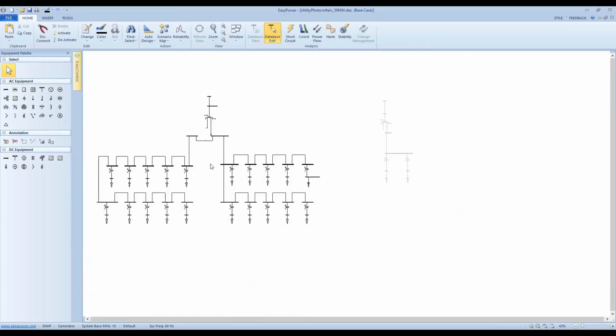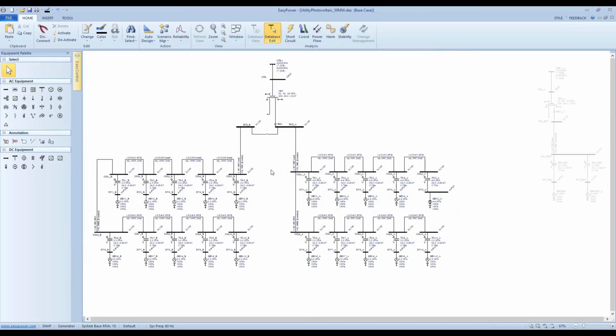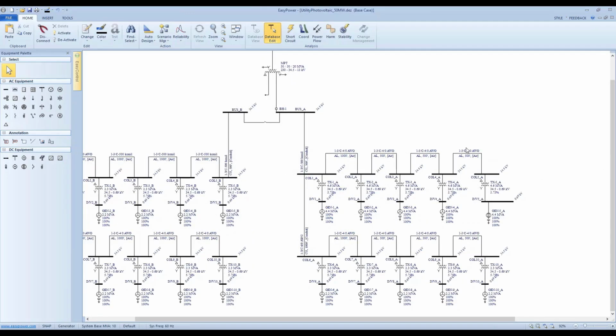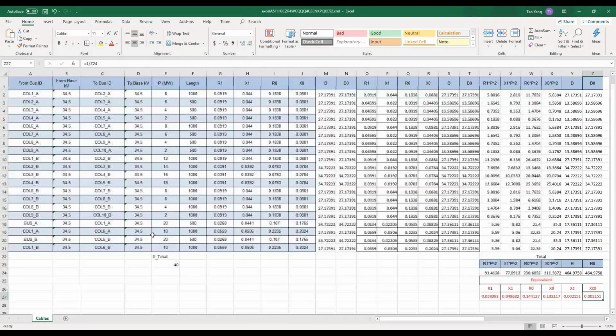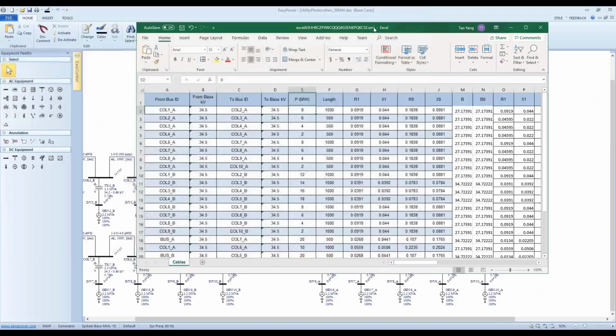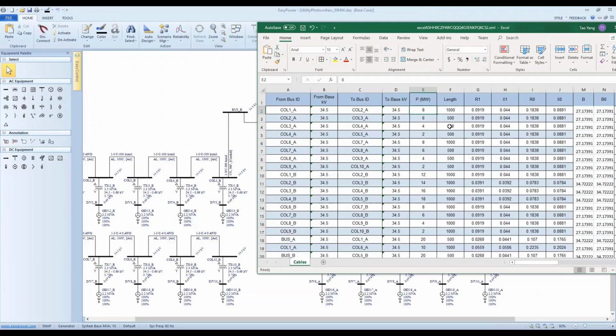By comparing this 50 megawatt design with the 40 megawatt design, we know that we don't have any topology change. We don't have any impedance change of the circuit. The only thing that has changed is the power flow through some circuits, specifically from bus 1A to collector 1A, collector 1A to 2A, 2A to 3A, 3A to 4A, and 5A. So we can use the same spreadsheet, but just change the power flow on each circuit that has been modified to come up with my new collector system equivalent.